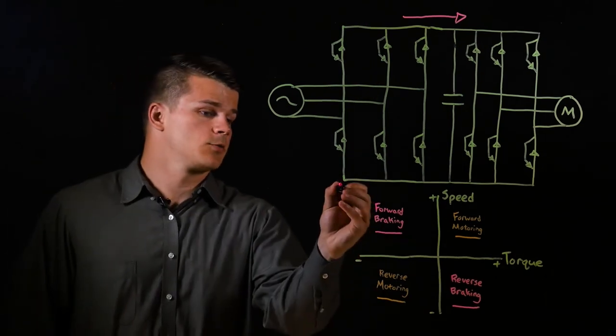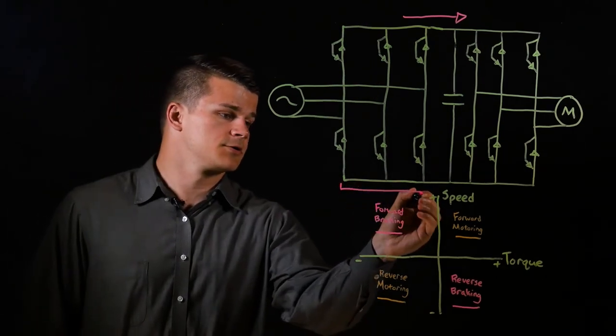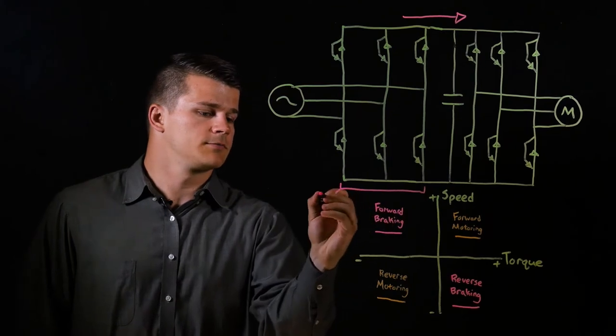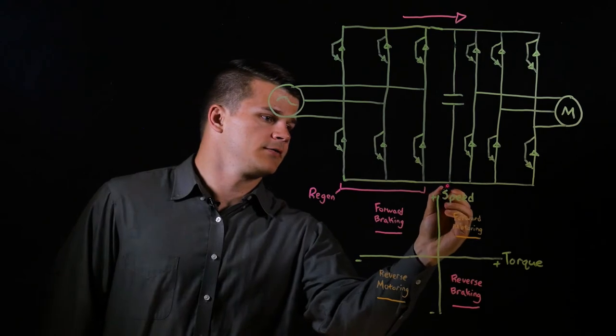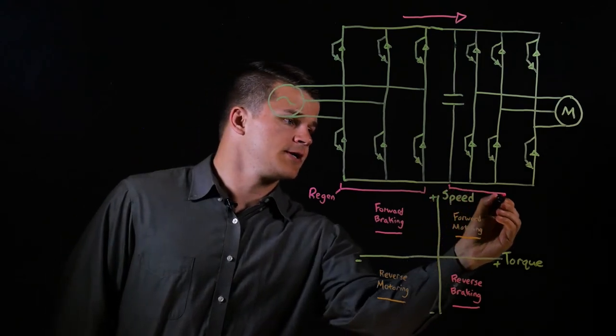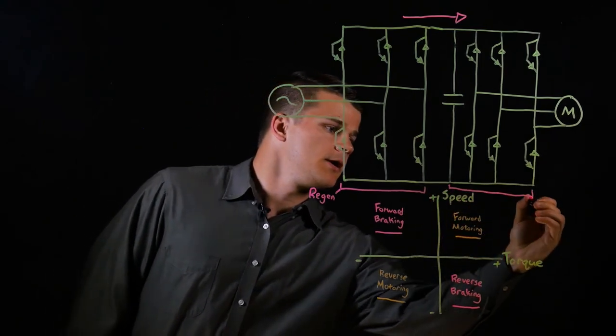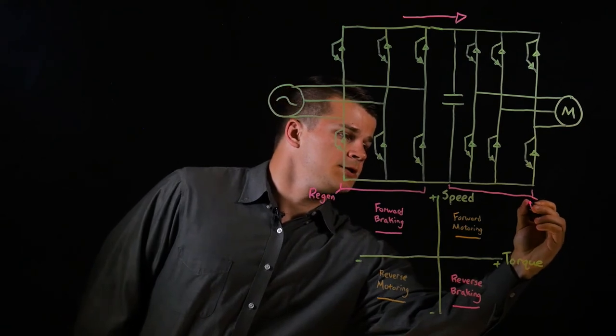A line regen unit essentially replaces the input rectifiers to the drive. So you'd have your line regen portion of the topology here, and then on the right-hand side, you would keep your standard DC bus and output IGBTs of the drive.